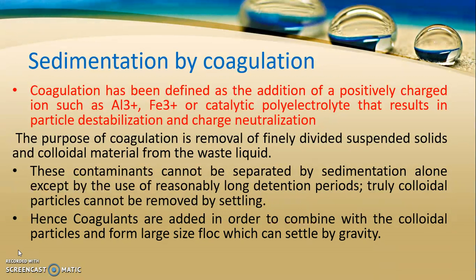Colloidal particles, when they combine with chemical coagulants, become large in size and thus settle down by weight. Coagulation is defined as the addition of positively charged ions such as Al³⁺ (aluminium) or Fe³⁺ (iron), or catalytic polyelectrolyte, that results in particle destabilization and charge neutralization. Since colloidal particles carry a negative charge, the positively charged coagulants destabilize them, causing them to combine and settle down.